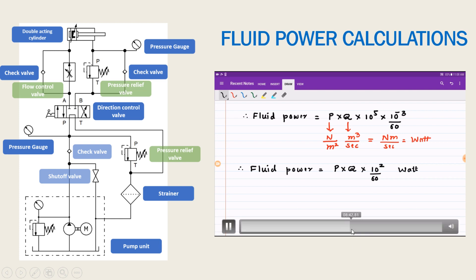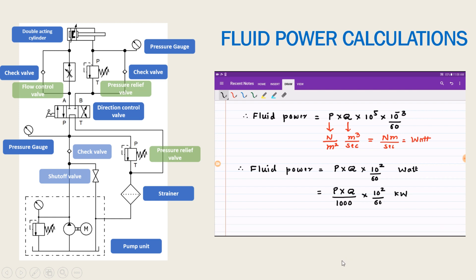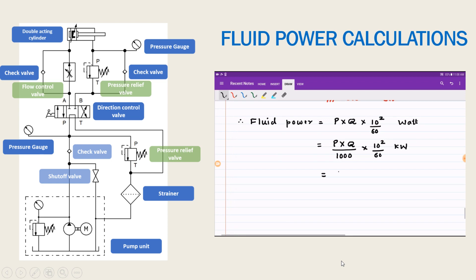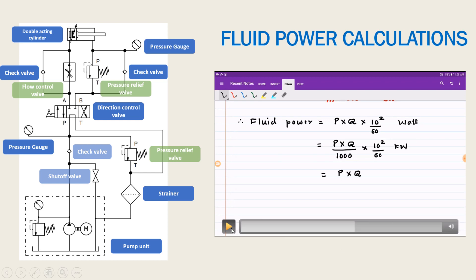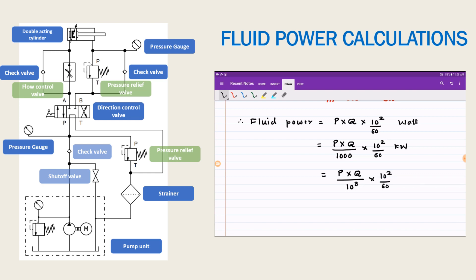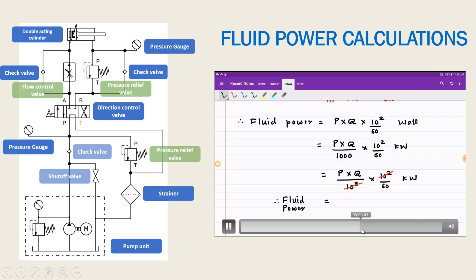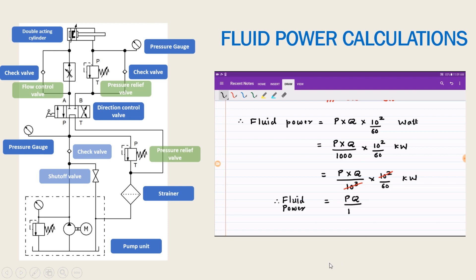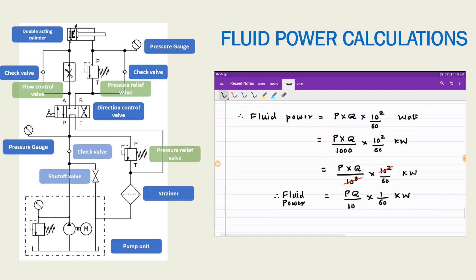This result is in watt. To convert to kilowatt we divide by 1000, so we have p times q times 10 to the power 2, divided by 60, then divided by 1000. In the denominator we have 60 times 10, which is 600. Ultimately, fluid power equals p times q divided by 600, in kilowatt.